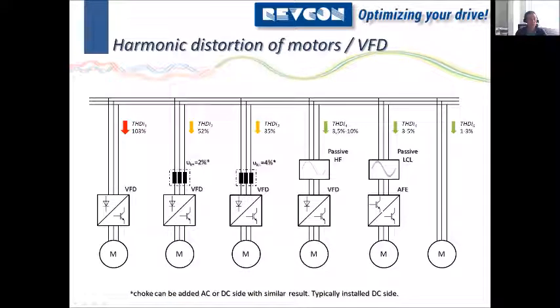So next step would be an active front-end solution. You will typically have a THDI of 3 to 5%. And the main difference between this technology and a standard drive is the input of the drive itself. So if we look at the standard drive right here, we have a diode rectifier input. But if we look at this one, by adding a high switching frequency to the IGBT, we can define the resistance of the input, which means that we can decide how the input current will look like, so we can get the sine wave shape on the input side.